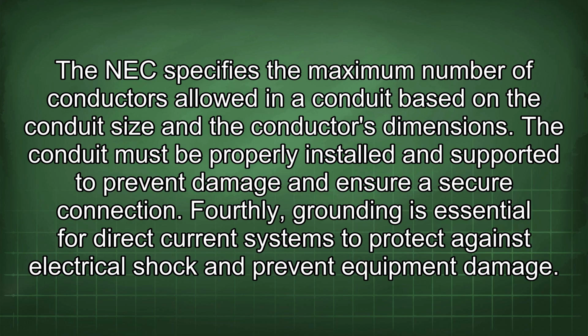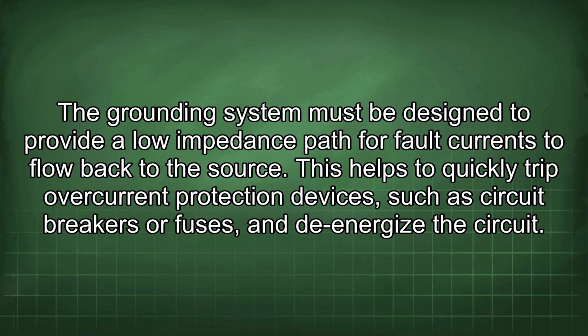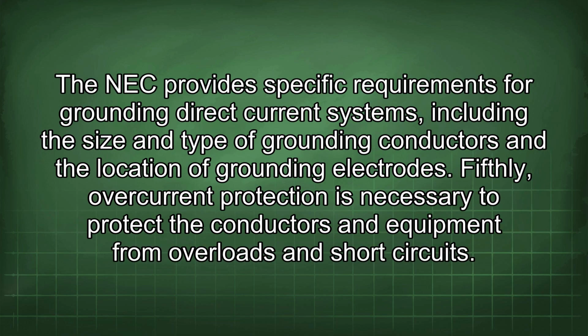Fourthly, grounding is essential for direct current systems to protect against electrical shock and prevent equipment damage. The grounding system must be designed to provide a low impedance path for fault currents to flow back to the source. This helps to quickly trip overcurrent protection devices, such as circuit breakers or fuses, and to de-energize the circuit. The NEC provides specific requirements for grounding direct current systems, including the size and type of grounding conductors and the location of grounding electrodes.